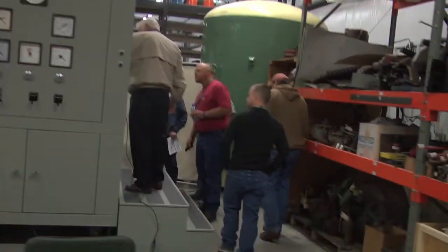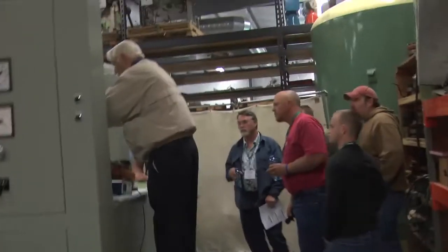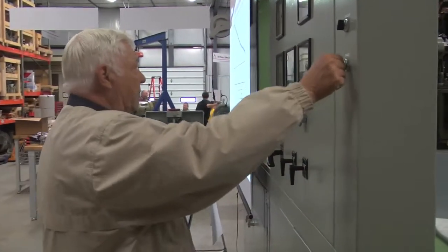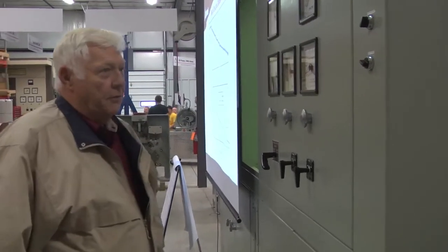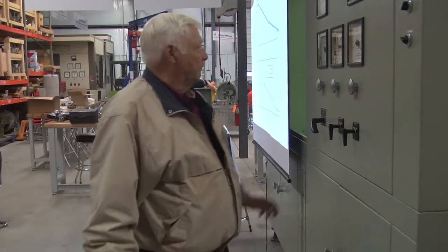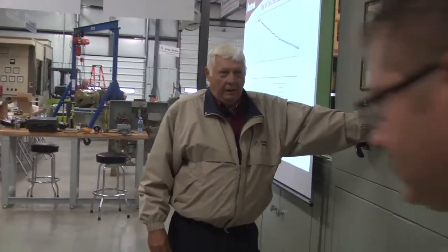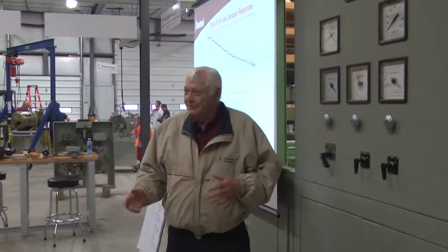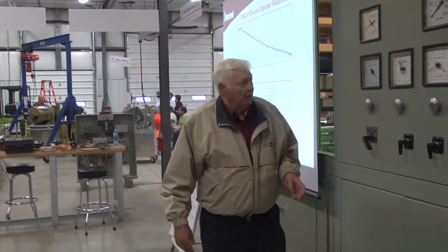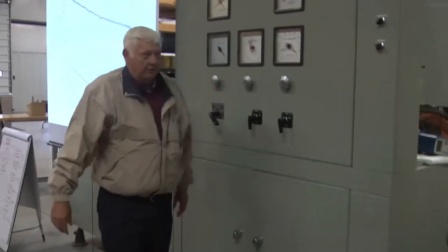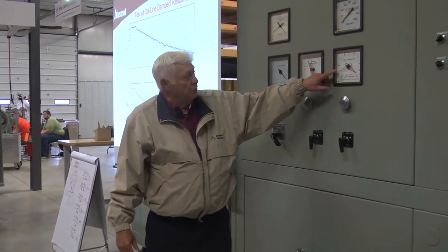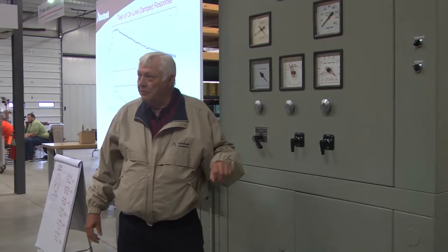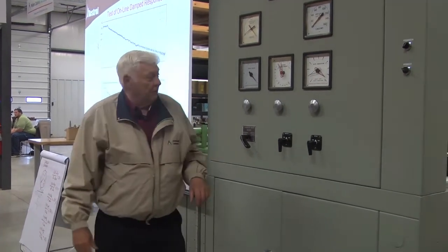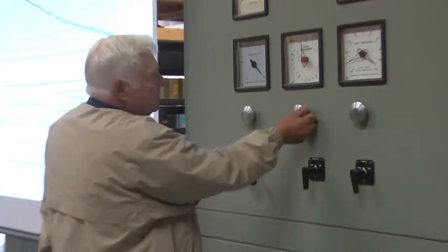So one of the things we can do is I'm going to close the dash pot needle all the way. I'm going to take us offline. Now if we come over here in the front, I'm going to give it a step change. And you never know if it's going to work or not because we haven't done this, but I'm going to give it a speed adjustment change. And what I expect to see is the gates make a movement and stop. That'll tell us how much proportional gain we have on the unit, okay? So somebody else is going to have to help me watch, okay?